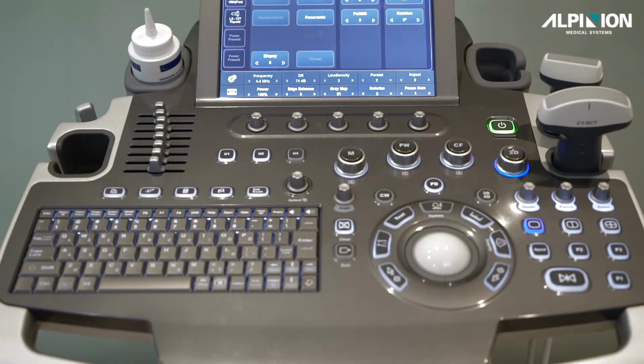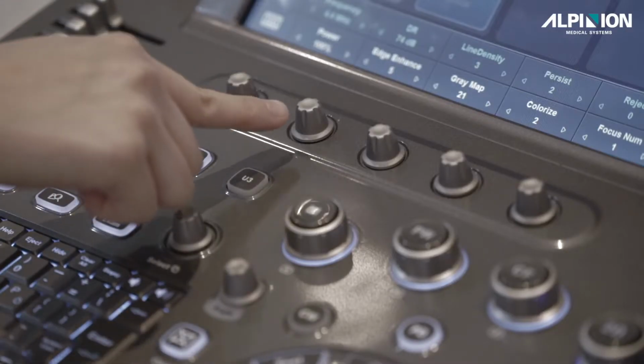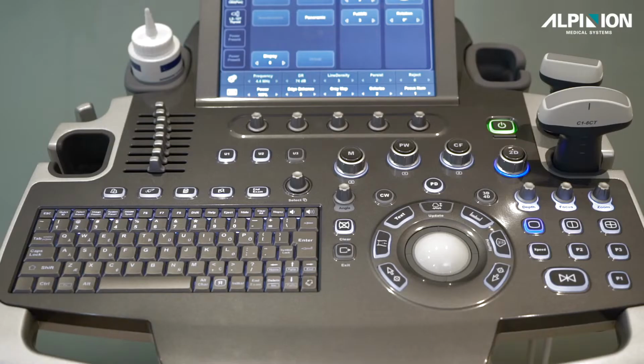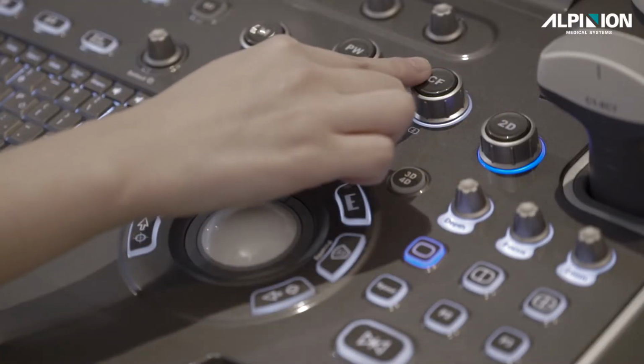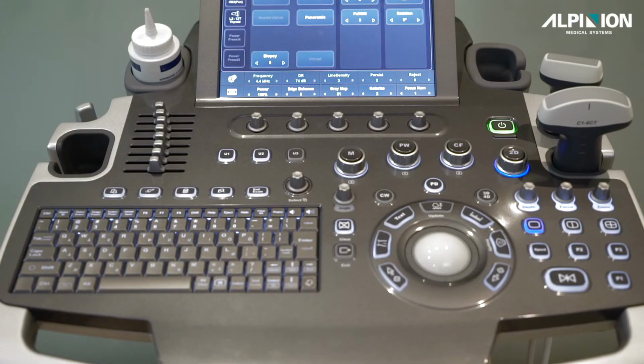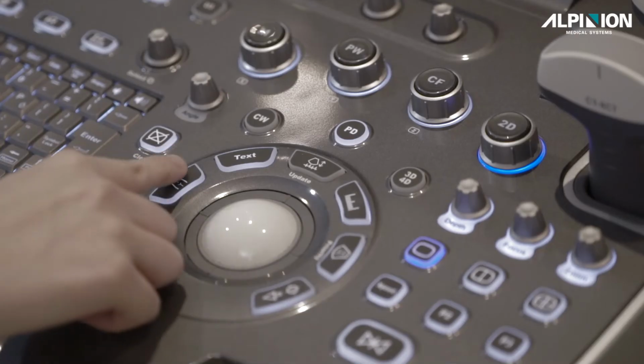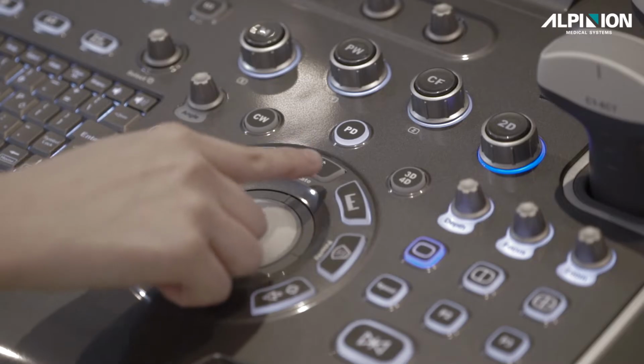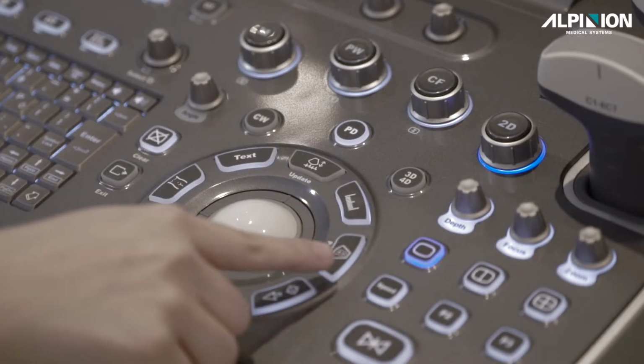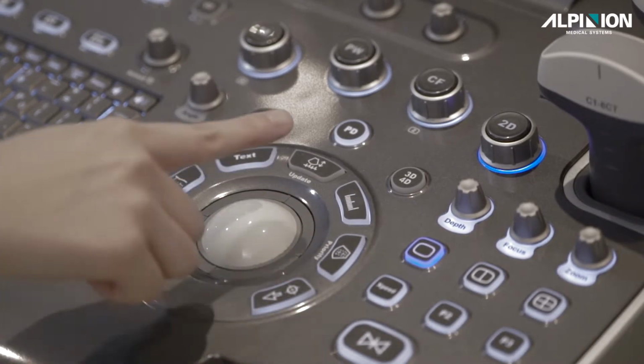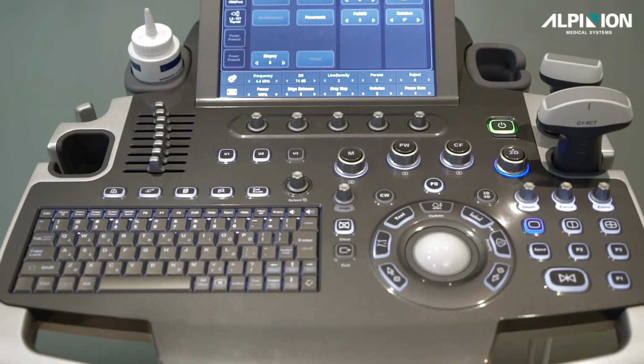Along the upper side of the control panel, we have 5 rotary keys to control any imaging parameters or functions in each imaging mode. Just below these rotary keys, we have the Imaging Mode Zone, and each Imaging Mode button is able to function as its gain control. Around a trackball, you will find many buttons such as Cursor, Body Pattern, Text, Update, Measure, Priority, and Set button. The Update key is used to reactivate 2D mode and pause a Doppler image when using a triplex mode.